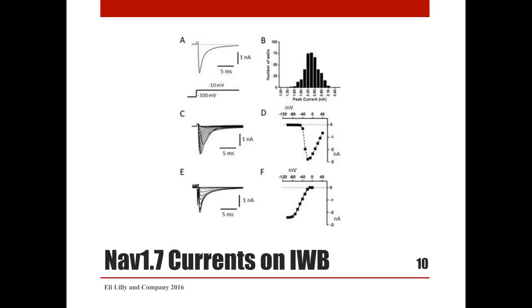This is a look at NAV1.7 currents recorded on IonWorks Barracuda in population patch mode. A depolarizing step evokes a current that rapidly activates and inactivates, as shown in panel A. The distribution of currents was relatively narrow, shown in panel B. The average amplitude was around 2.5 nanoamps. Panels C and D show activation with a threshold at minus 50 mV and peak around minus 20 mV. Panels E and F show inactivation with a half-inactivation voltage of minus 50 mV. Overall, NAV1.7 properties on Barracuda looked comparable to manual patch recordings.